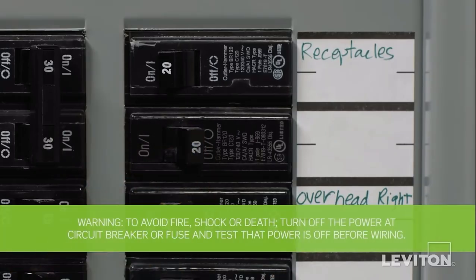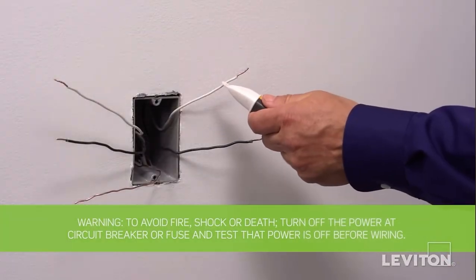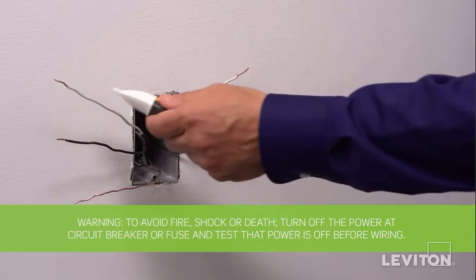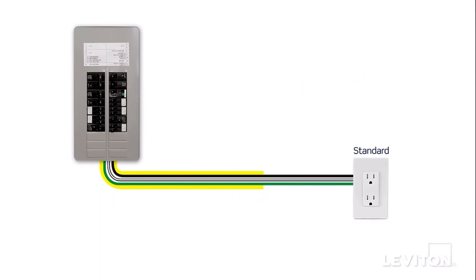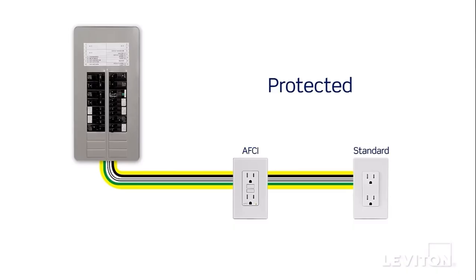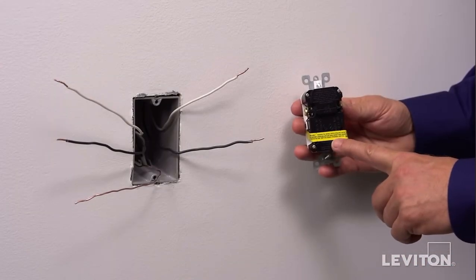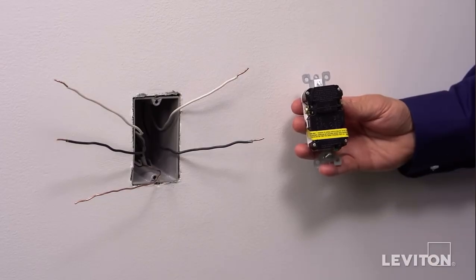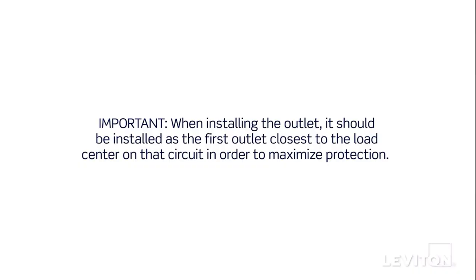Be sure to turn the power off at the circuit breaker and use a voltage tester to ensure that the power is completely off. AFCI, GFCI, and dual function outlets feature what is called feed-through protection. This means the protection in the device can be extended to other outlets on the circuit that are downstream from the device being installed. This is done by attaching the wires that lead to the downstream outlets onto the terminals that are marked load. Important: when installing the outlet, it should be installed as the first outlet closest to the load center on that circuit in order to maximize protection. If you're not certain which outlet is the first, contact an electrician.